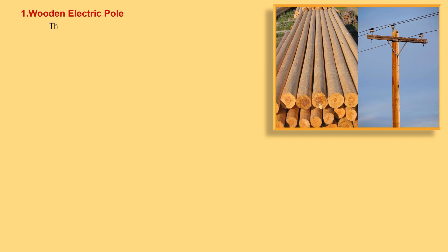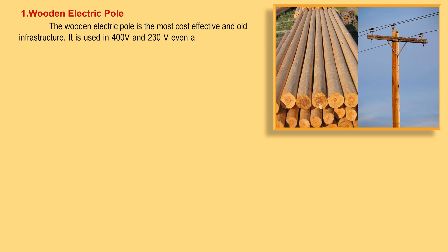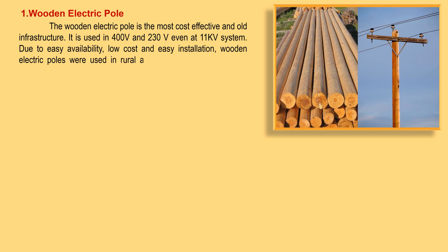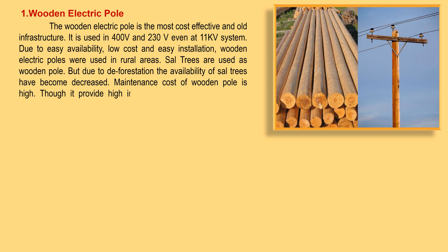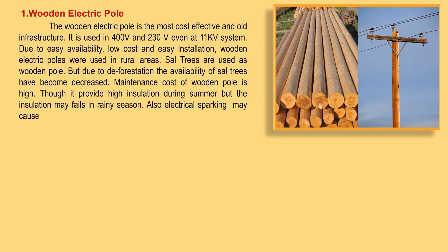The wooden electric pole is the most cost-effective and old infrastructure. It is used in 400V and 230V, and even at 11kV systems. Due to easy availability, low cost, and easy installation, wooden poles were used in rural areas. Sal trees are used as wooden poles, but due to deforestation their availability has decreased. Maintenance cost of wooden poles is high. Though it provides high insulation during summer, the insulation may fail in rainy season, and electrical sparking may cause a fire on the wooden pole.